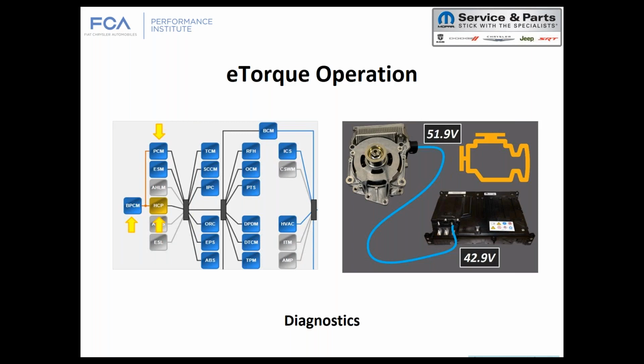This is a 48 volt system. If battery voltage gets above 51.9, the system shuts down and turns on a check engine light. If battery voltage goes below 42.9, we shut the system down and turn on a check engine light. This protects all of the control modules and the unit itself, so we have a range of about a 9 volt operating range we want to stay within.